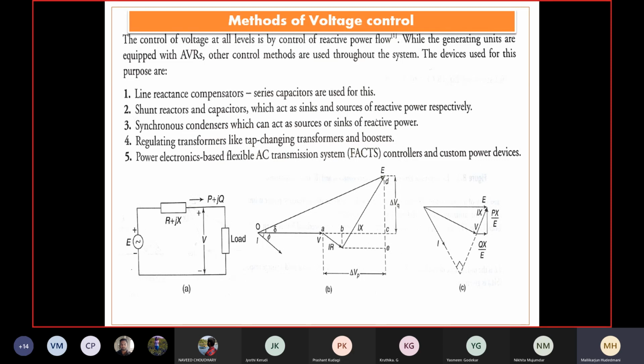It is to highlight the use of shunt capacitors and reactors in a system in accordance with your requirement. As per the load, as per the delivery, switch them on, switch them off, or eliminate them in part or full according to the requirement, such that such management also makes the requirement of reactive power in step, which in turn improves your voltage profile. That was seen by the adoption of shunt reactors and capacitors.